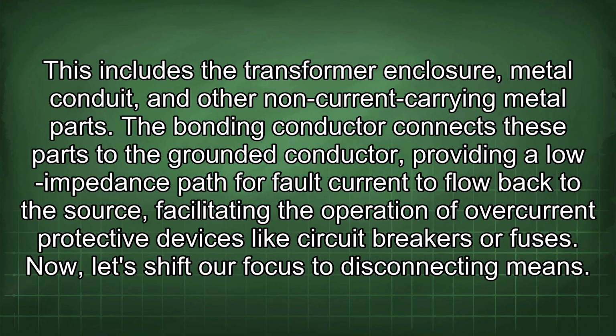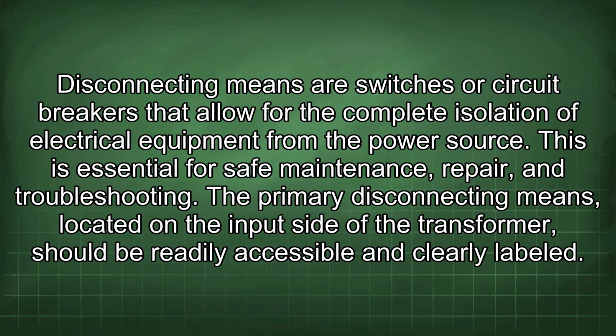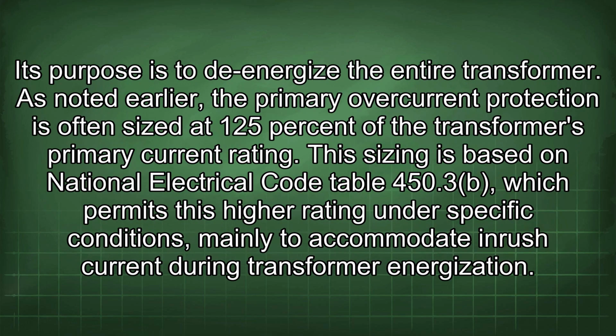Now let's shift our focus to disconnecting means. Disconnecting means are switches or circuit breakers that allow for the complete isolation of electrical equipment from the power source. This is essential for safe maintenance, repair, and troubleshooting. The primary disconnecting means, located on the input side of the transformer, should be readily accessible and clearly labeled. Its purpose is to de-energize the entire transformer.